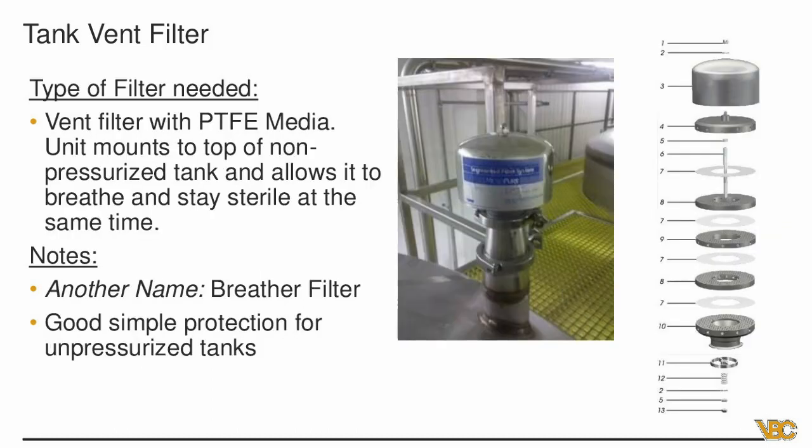Type of filter you need: anytime you're talking air and gases, it's pretty much always the same type of filter. It's a Teflon or PTFE media. The units typically mount on top of a non-pressurized tank, and they allow it to breathe air in and breathe air out while staying sterile inside the environment. Typically they're called a vent filter or tank vent filter. Another name for it is a breather filter because the tank's literally breathing. Depending on the pressure ratings in your tanks, that's normally taken into account when these are sized. And last, it's just real good, simple protection for unpressurized tanks.